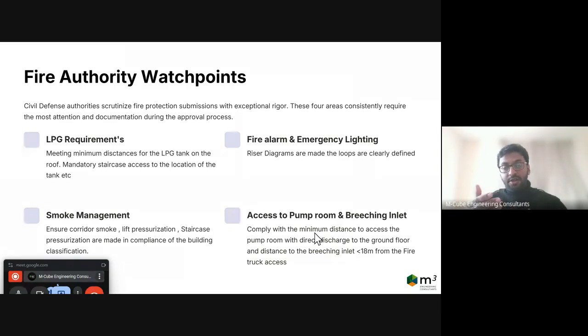Again, you need to ensure you have smoke management for staircase pressurization, corridor, and lift pressurization. If it's a G plus 50 building, there is a compliance requirement for a dedicated enclosure for the lifts, so that's something to look out for. Also, a fireman lift lobby is mandatory for a high-rise building, though not for a low-rise or mid-rise building. For high-rise buildings, the authority mandates a fireman lift lobby, and pressurization is also needed. We need to be aware of these things already mentioned in the code and ensure they are implemented at the design stage.